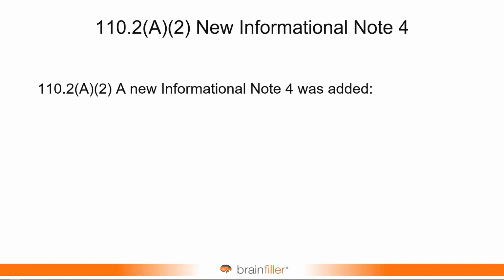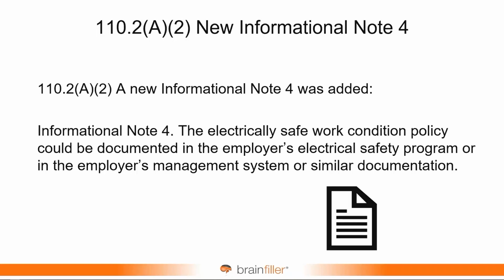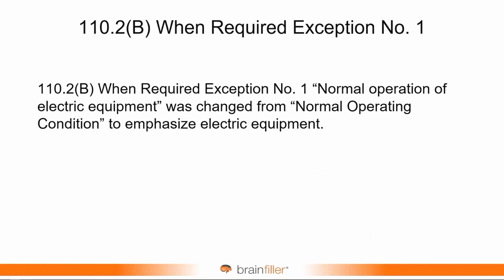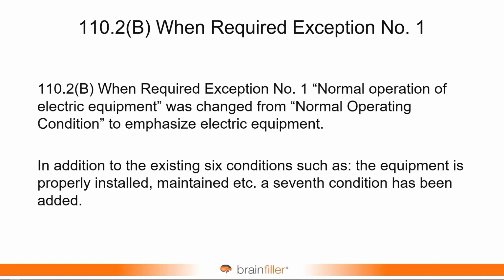110.2A1. There was an informational note that was added to 110.2A2, and the informational note is that the electrically safe work condition policy could be documented in the employer's electrical safety program or in the employer's management system or similar documentation. There's also a revision. It's really kind of a text revision, and this is when required. Normal operation of electric equipment. It used to be referred to as normal operating conditions, and it was changed to normal operation of electrical equipment. Now, this is where you find the 6 conditions that define the normal operation of electric equipment.